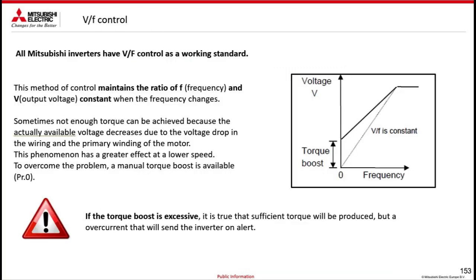We said that V on F is a standard control that keeps the voltage to frequency ratio constant, 1:1. But notice from this graph that there is almost an offset at the start. As I said before, since V on F keeps the ratio constant, at very low frequency the torque could be approximately zero. And this is a problem for a synchronous motor. So I falsify the starting voltage by adding a real booster. In fact, it is called torque boost, which is parameter 0, a percentage referred to the nominal voltage. This extra voltage allows me to start with a torque that is clearly higher than the actual one.